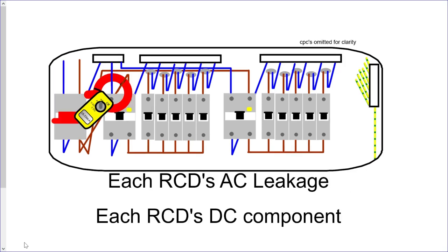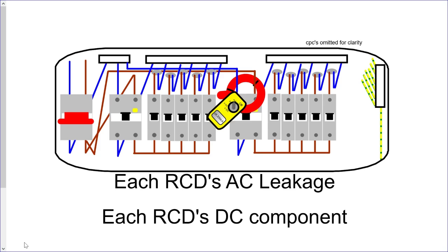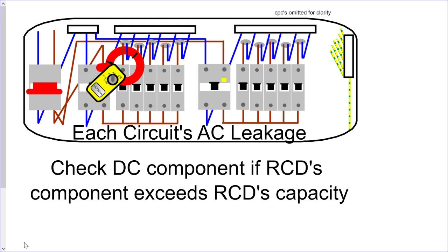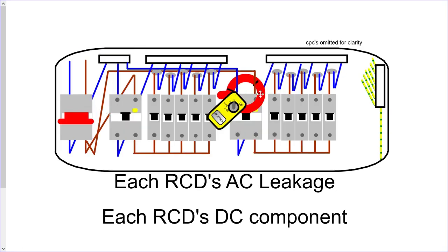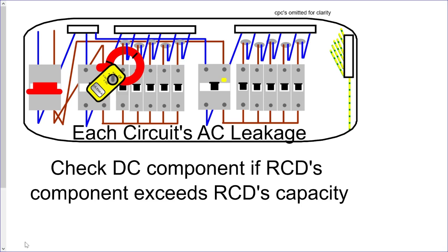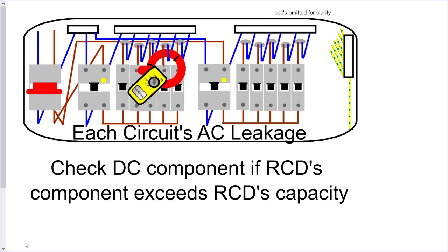Then we test each RCD, checking the AC leakage and the DC components flowing back through that residual current device. Okay, so we check each one of these RCDs, taking a note of AC and DC currents. All right, and then you would then test each individual circuit. Again, AC leakage definitely, but you might also check the DC components if, when you were back at this stage, you identified that the DC component here was more than what the device is rated for. Okay, so taking a note of these values as you test through the circuits. Okay.